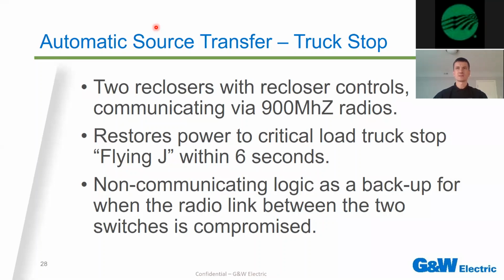First one is an automatic source transfer. When I was talking about critical loads before, that is one of these examples. It's very straightforward, with fast deployment and fast return on investment when it comes to automation. In this scenario with a co-op in Missouri, it's protecting a truck stop. We're talking about two reclosers, communicating wirelessly through 900 megahertz radios, restoring power to this critical load — a Flying J travel center — within 6 seconds. So while before the truck stop experienced outages in the range of hours, now if there's an issue on the overhead lines supplying power, an alternate source can switch in within 6 seconds.